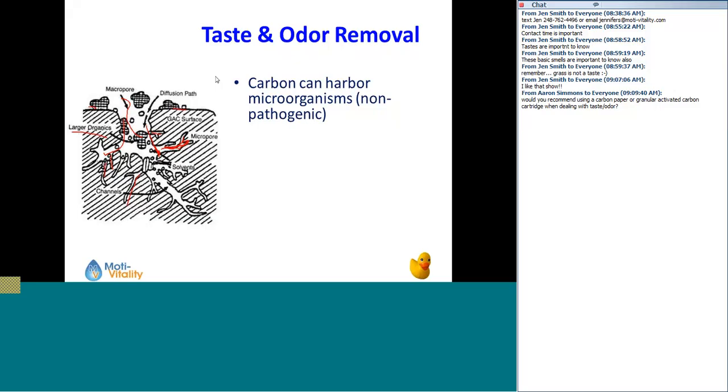So there are some companies out there who put those big carbon tanks in the pre-position when there's iron in the water, knowing that you're going to have to change the carbon a little more often in that position, but understanding that the water softener will then take the iron out, so you don't have to worry about the carbon getting iron fouled and having to prematurely change it. I know probably all of you listening, none of your customers ever forget to put salt in their water softeners or bypass them accidentally or whatever, but believe it or not, some people have customers out there that don't maintain their softeners properly.